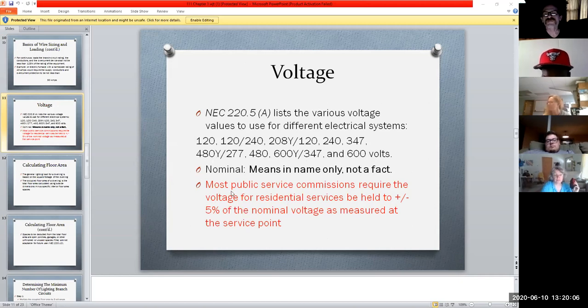And just like a little highlight, most public service commissions require the voltage for residential services to be plus or minus 5% of the nominal if they measure it at the service point. And where's the service point? That's coming in where your meter's at. From the transformer to your meter is considered your service point, because that's where they deliver power to. After that, of course, now it's your side. After the meter, it's residential. Before the meter, it's considered service, or the service delivery from the power company.